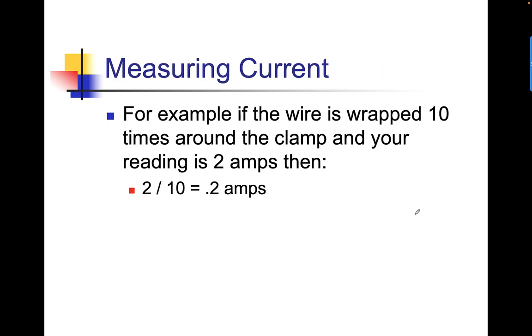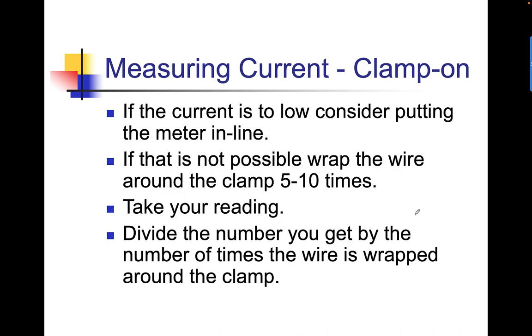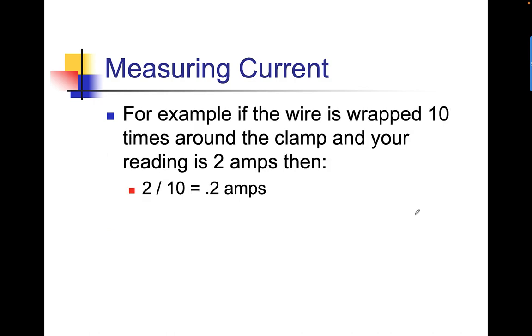You can also maximize the reading by wrapping the same wire on the same side of the circuit — like 10 times around the clamp — and if your reading is 2 amps, divide it by 10 to come up with 0.2 amps. If the current is too low, put the meter in line. If that's not possible because of voltages, wrap the wire around the clamp 5 to 10 times, take your reading, and divide the number you get by the number of times the wire is wrapped around the clamp. For example, if the wire is wrapped 10 times and your reading is 2 amps, then 2 divided by 10 is 0.2 amps.